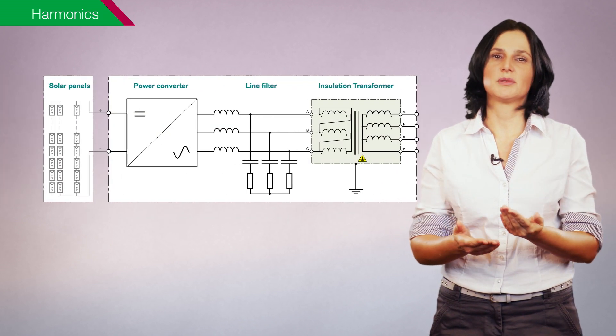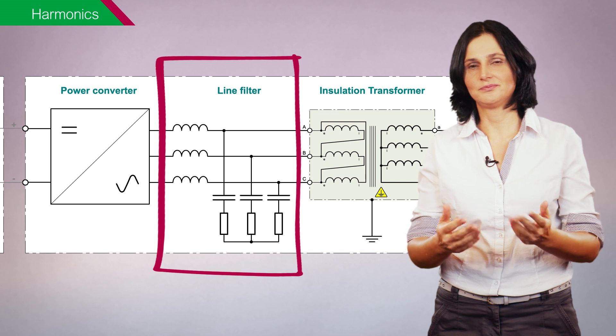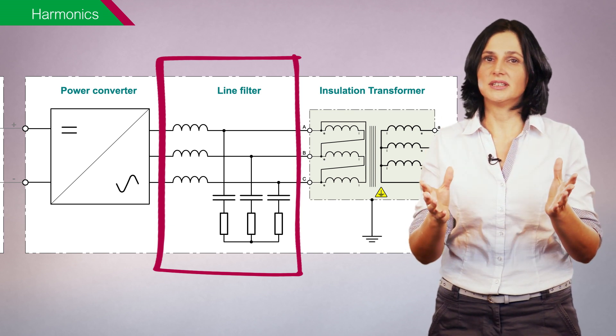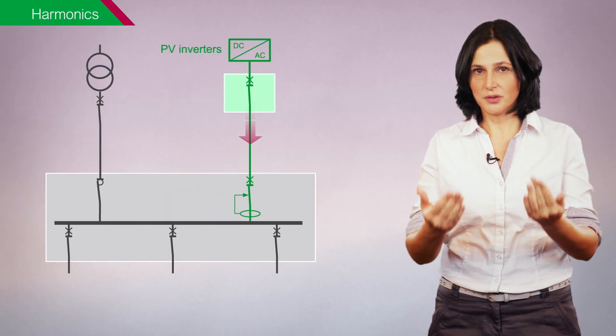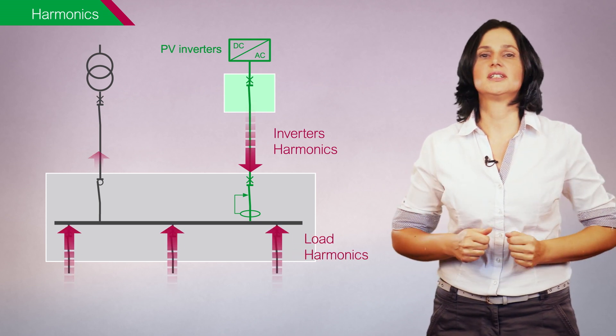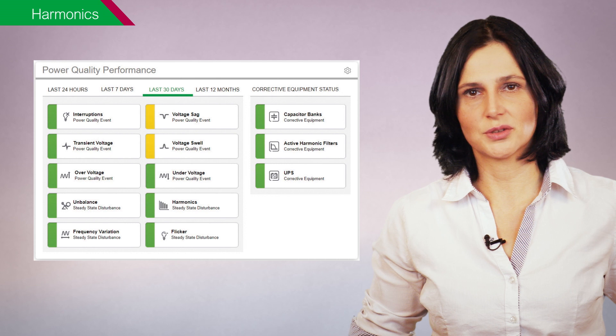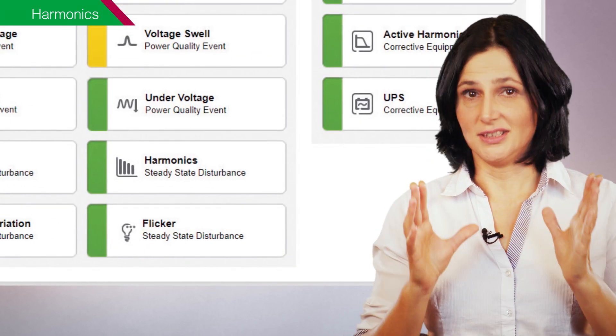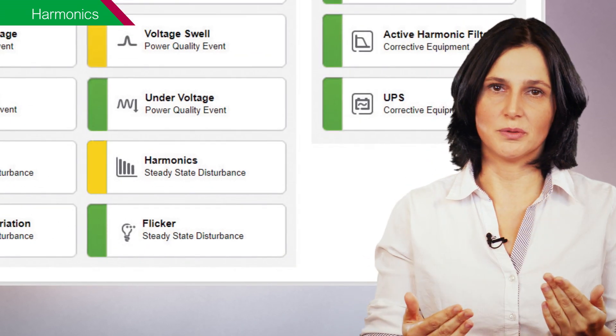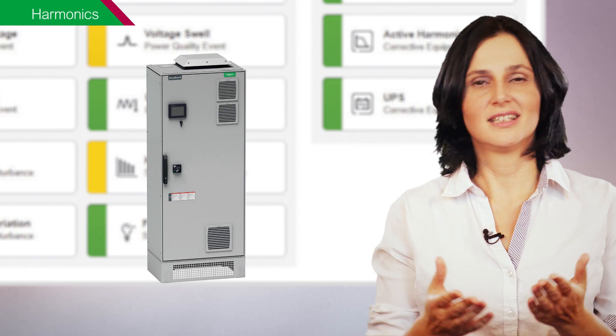This harmonic disturbance generally remains within an acceptable range because photovoltaic inverters have integrated harmonic filters. However, the overall harmonic distortion in the electrical installation can be higher because the harmonics injected by the photovoltaic inverters are combined with those generated by the loads. Therefore, it is recommended to supervise harmonics in the electrical installation, and if the overall harmonic level is over the acceptable limits, harmonic mitigation measures such as active or passive filters can be added.